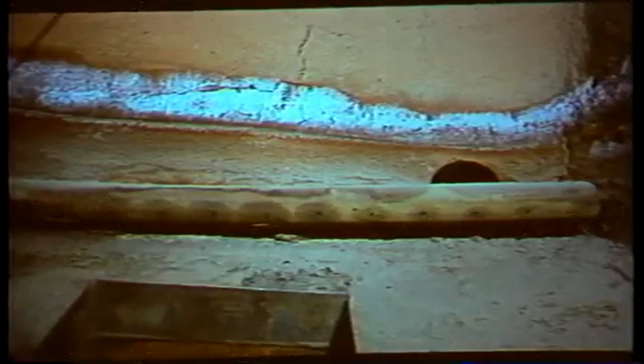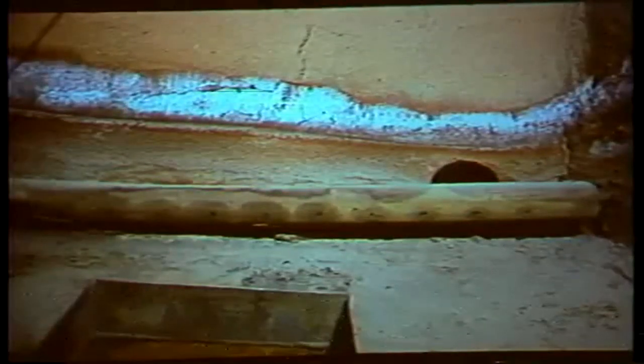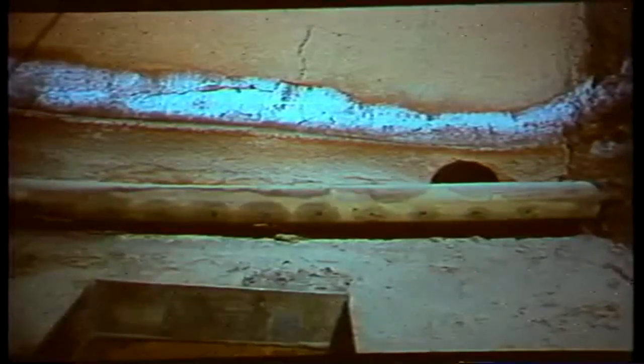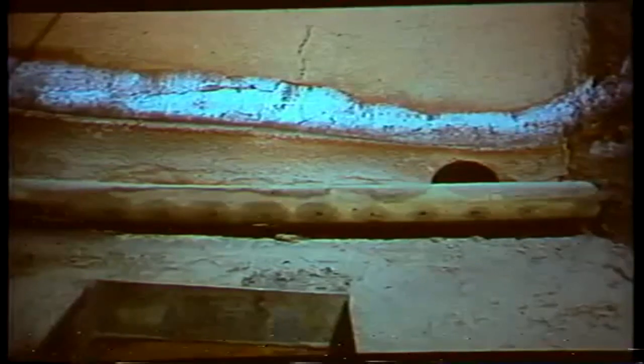Most ash hoppers use pressurized water to stir up the bottom ash being removed from the boiler — this helps get all the ash out. Pipes and nozzles are used to direct the water spray. You must inspect these pipes and spray nozzles for ash blockage and misalignment caused by clinkers falling on them. The nozzles are aligned correctly if they direct their spray towards the ash gate — that is where the ash leaves the boiler. The nozzles should not spray directly at the refractory, as that will wear it away.